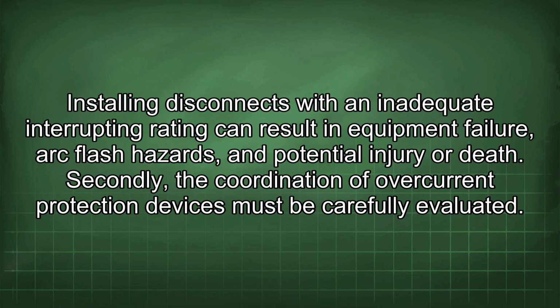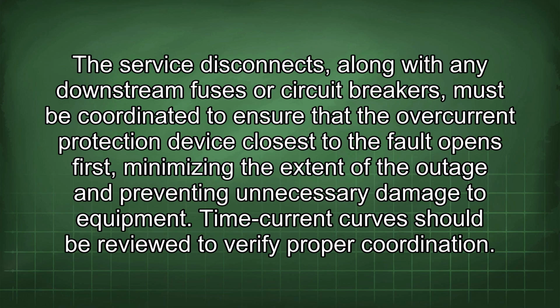Secondly, the coordination of overcurrent protection devices must be carefully evaluated. The service disconnects, along with any downstream fuses or circuit breakers, must be coordinated to ensure that the overcurrent protection device closest to the fault opens first, minimizing the extent of the outage and preventing unnecessary damage to equipment. Time current curves should be reviewed to verify proper coordination.